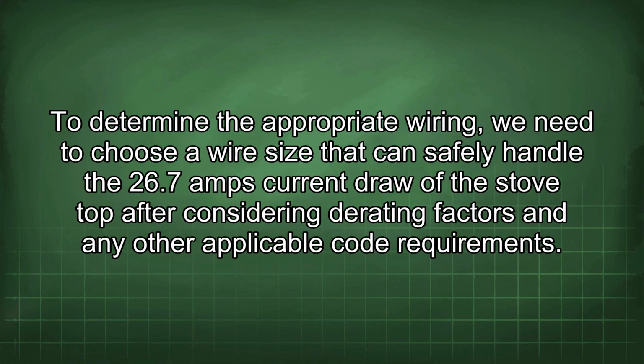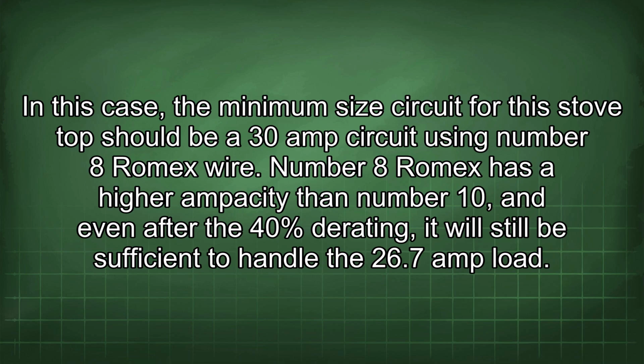To determine the appropriate wiring, we need to choose a wire size that can safely handle the 26.7 amps current draw of the stovetop after considering derating factors and any other applicable code requirements. In this case, the minimum size circuit for this stovetop should be a 30 amp circuit using number 8 Romex wire. Number 8 Romex has a higher ampacity than number 10, and even after the 40% derating, it will still be sufficient to handle the 26.7 amp load.